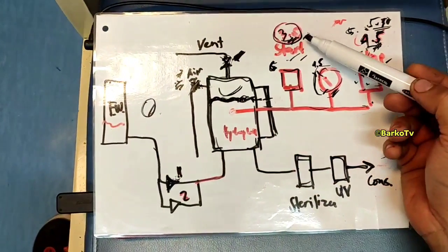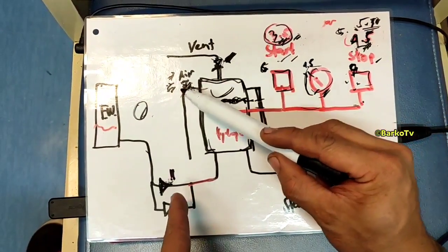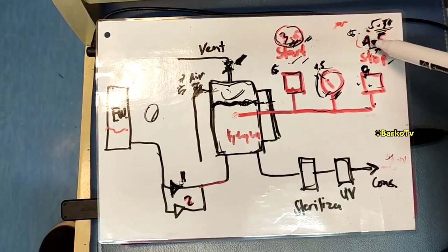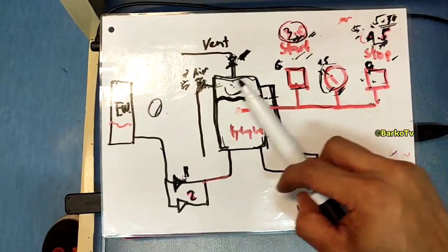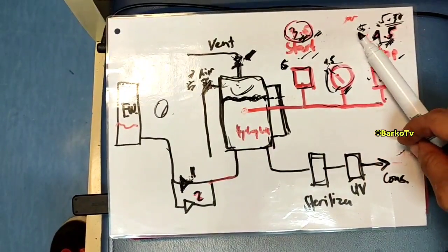Turn counterclockwise — half turn — to decrease the stop setting. After that, vent again so the pump starts at 3.5 bar. Then close the vent and open the air valve to fill the tank and build pressure up to the new setting. Continue feeding air into the tank until it reaches 4.5 bar, then check the new stop setting.